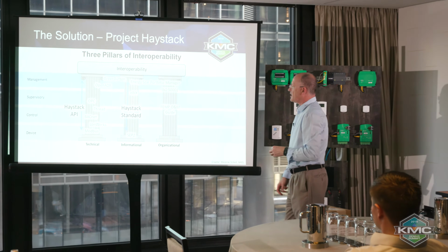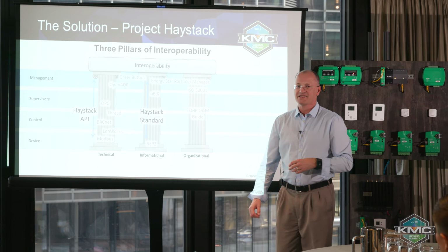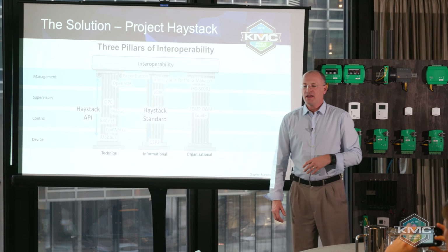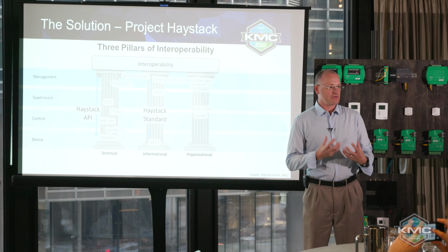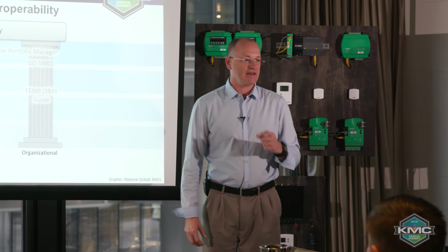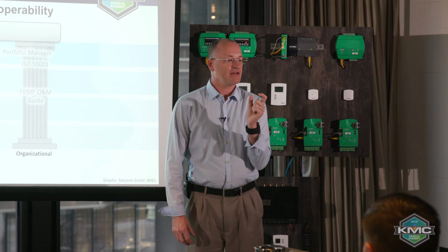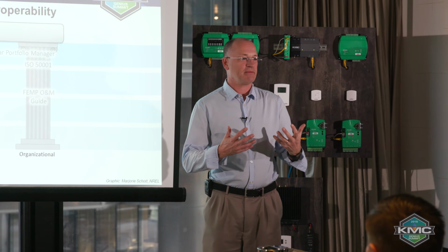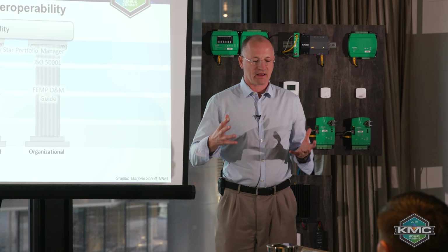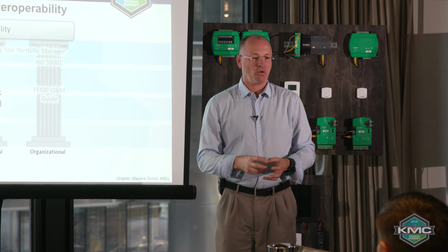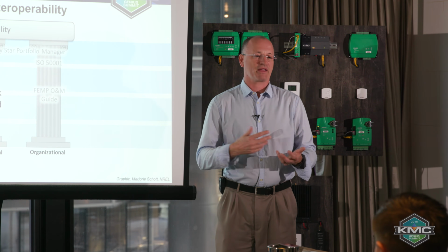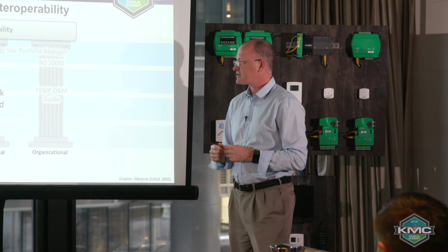Cool. How many people think Project Haystack is a naming convention? Anybody? Yeah, that's a very common misconception. It's not wrong, but it's not necessarily the root concept that I want to convey. We can work with naming. In fact, the name, better known as the dis, or display tag, is a legitimate tag inside a database, and we can use it in graphics and for queries. But the point is there's a bigger overarching metadata concept: if we put a little bit of information on that point, name being one, discharge temp, and sensor being two, three, and four, now any application can go get that information. And I'll give you some examples.